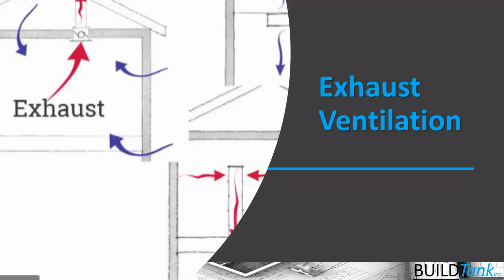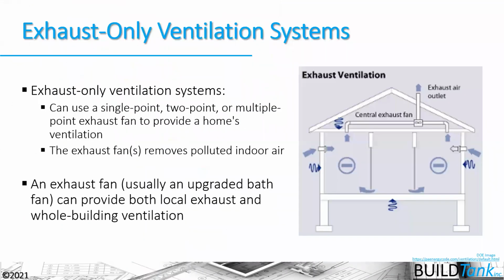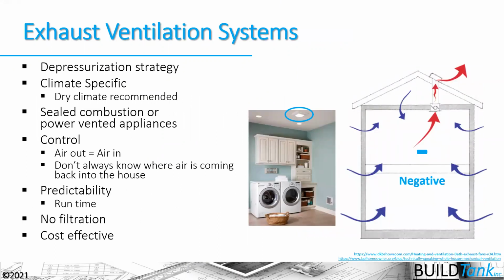Now, exhaust ventilation is kind of similar to supply ventilation, but the big thing to know here is that it is a negative pressure strategy. We're creating a negative pressure because we're sucking air out of the house. Any air that leaves the house has to be brought back in, either through a known opening or through random holes in the building envelope. So again, this is a climate-specific depressurization strategy. We like it in our dry climate here in Colorado because generally the air is drier outside the house than it is inside the house. So I'm bringing relatively dry air through my building envelope to the inside here.